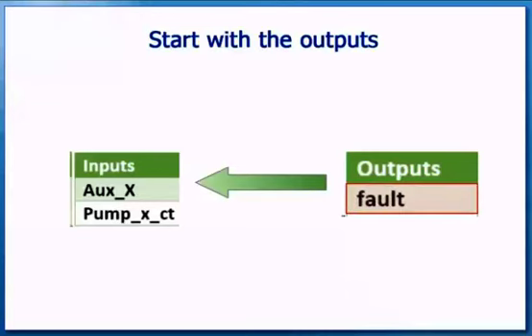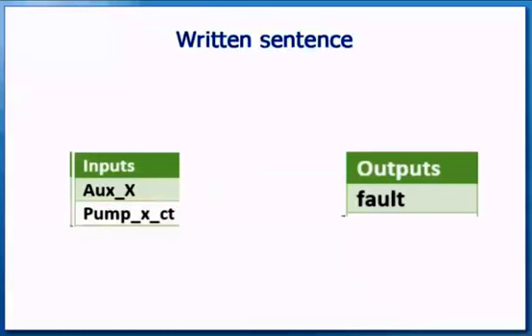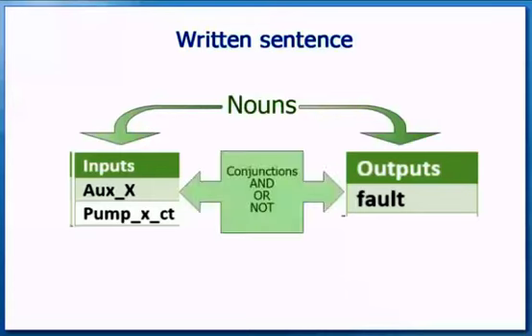Output 1 comes on when PUMPX is in fault. There is an auxiliary contact AUXX to tell us when the pump is switched on, and PUMPXCT to indicate that PUMPX is running. You can use a written English sentence to describe the operation, and from that sentence determine what the program will look like. The nouns are the inputs and outputs. AND means the inputs are in series, and OR means the inputs are in parallel.